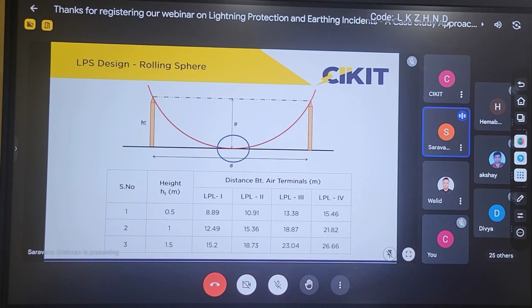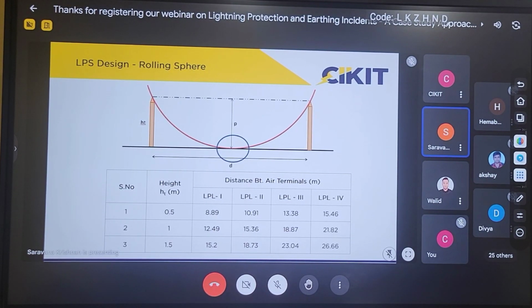For example, if I take a rectangle of size 12 cross 9, the length will be 12 meters and the width will be 9 meters. But if I measure the diagonal, it will be around 15 meters. So if I roll this imaginary sphere along the diagonal direction, then the sphere will make contact. So in the diagonal direction, the building is not protected. If I want to provide protection, the maximum distance should be maintained along the diagonal.